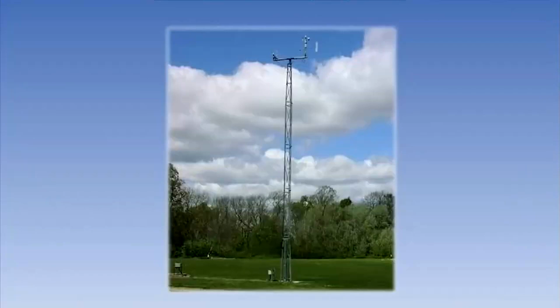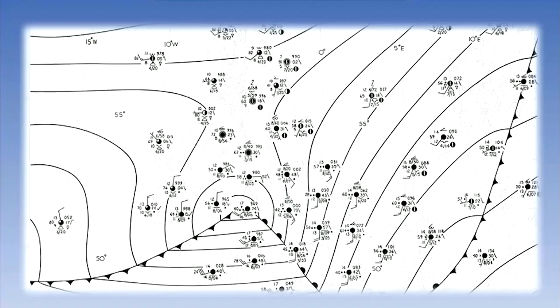These instruments are used around airfields to calculate the approximate surface wind velocity for aircraft either taking off or landing. The definition of the surface wind is one that blows at approximately 10 meters above ground level. The reason for this is that wind velocity changes dramatically with height and the very near surface velocity can be completely different from that a few meters above the surface. Consequently, these instruments are placed 10 meters above ground level and free of any nearby obstacles that may unduly disturb the flow of air and give misrepresentative readings.